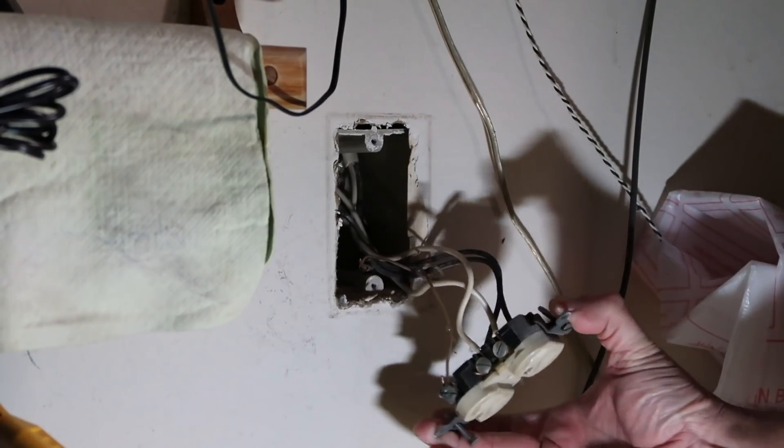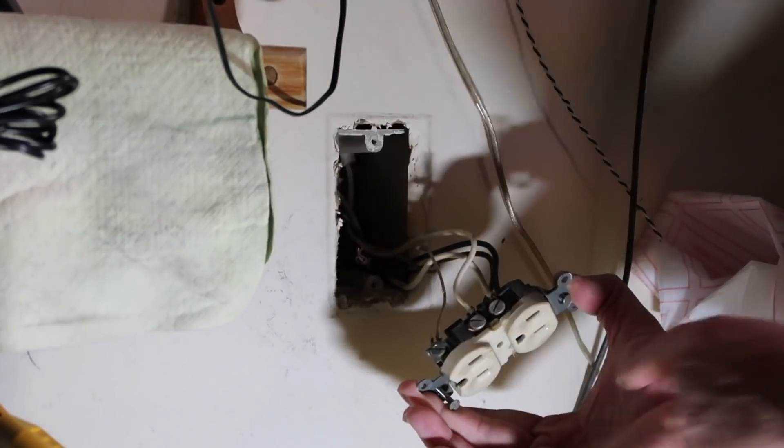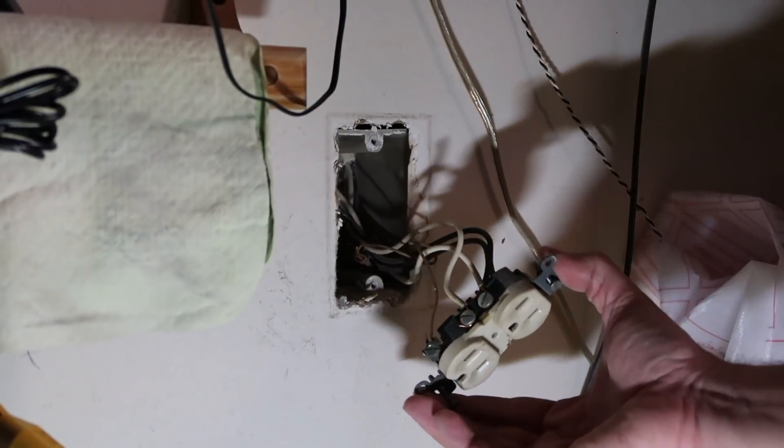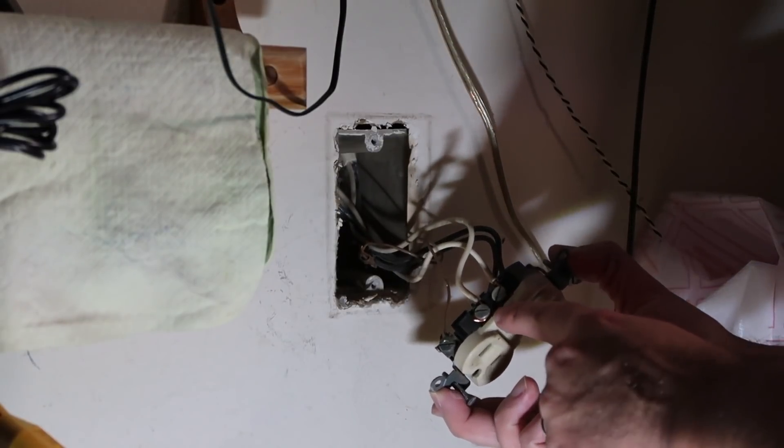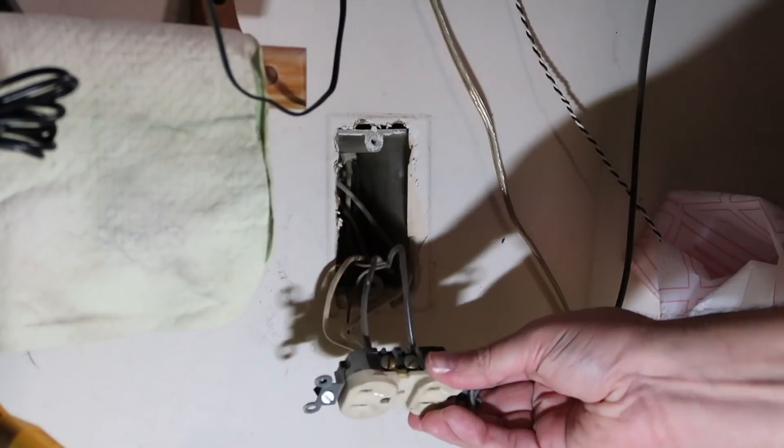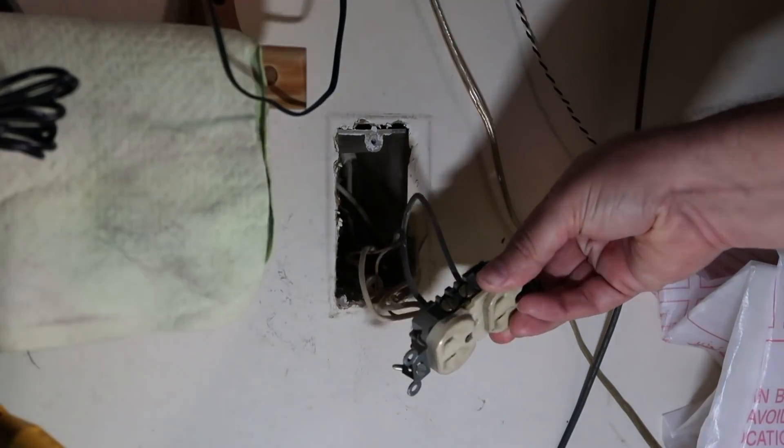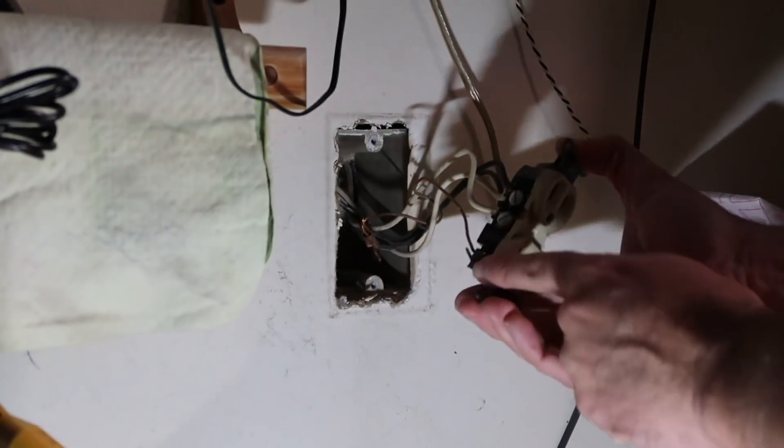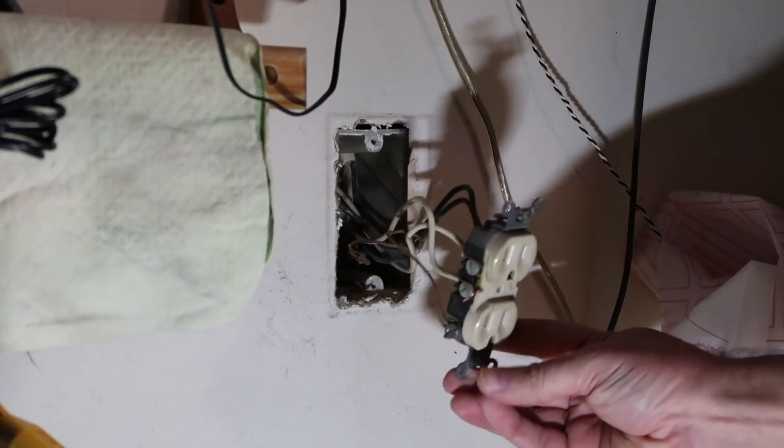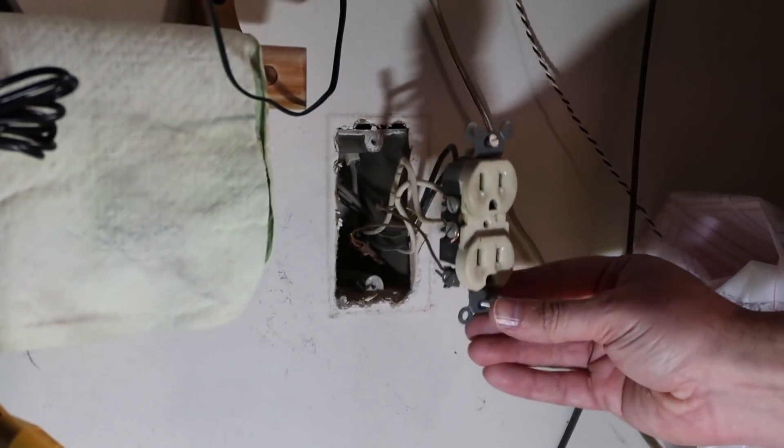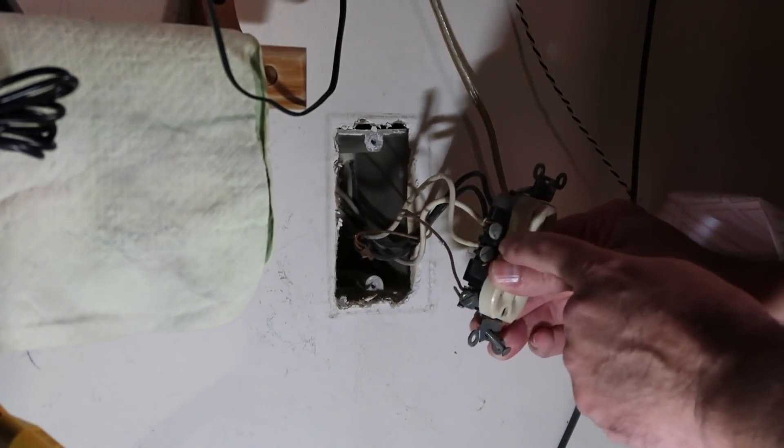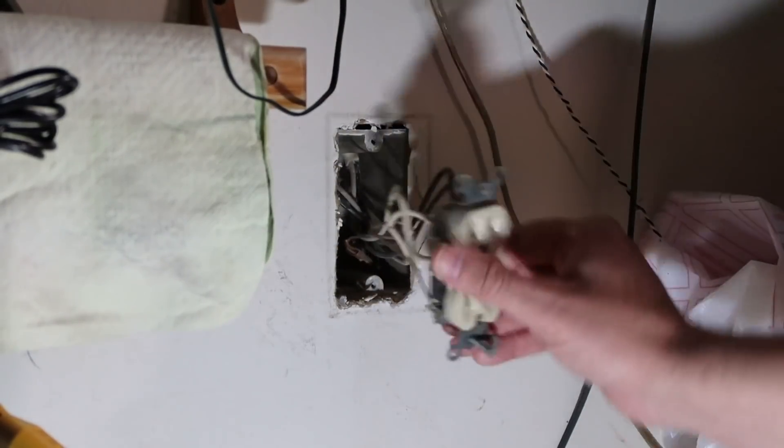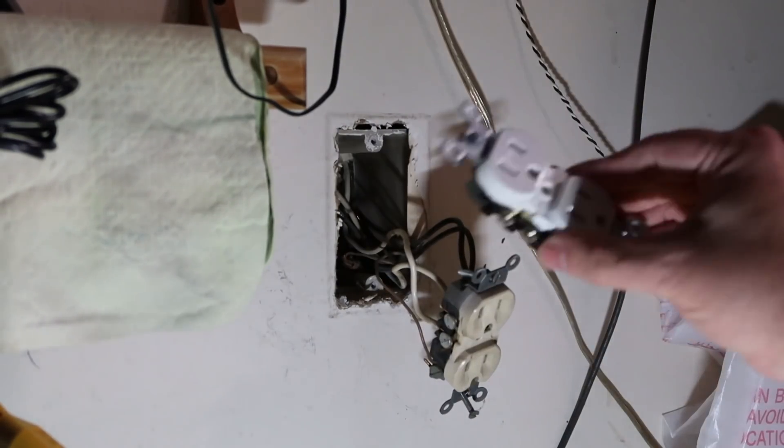And just in case it is still alive, which it's not, I always recommend just kind of pulling it out without touching the sides. So pull it out as far as you can. So as you can see here, there are white wires, black wires, and a ground. So what we want to do is usually what the standard is, white wires go to the silver screws, and the black wires go to the gold screws. Always. And then the ground just goes to the green ground.